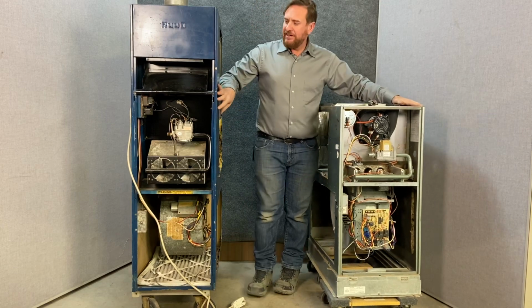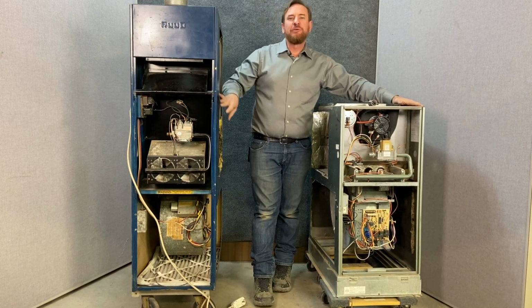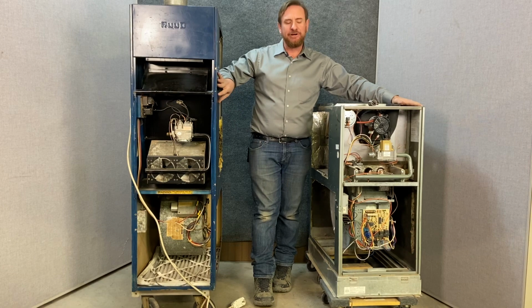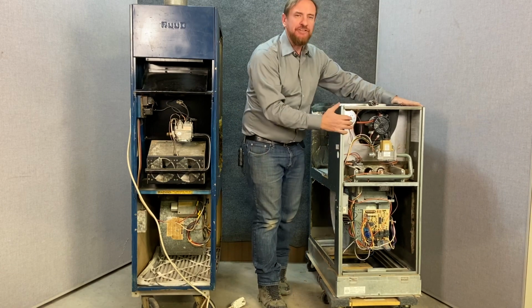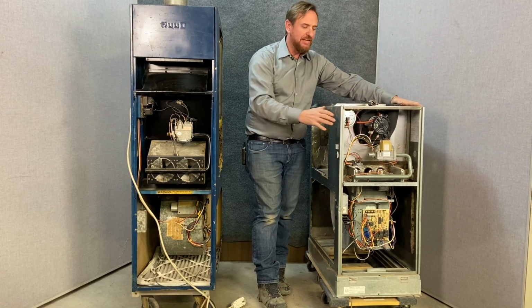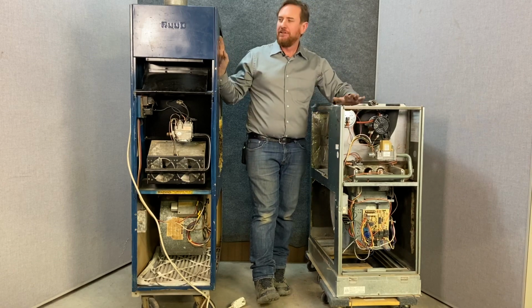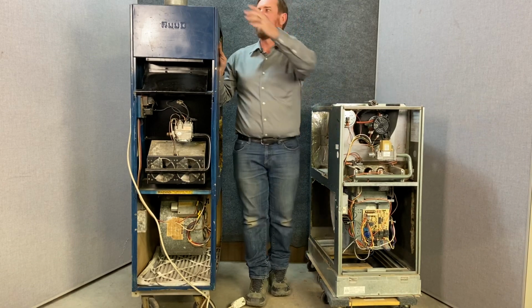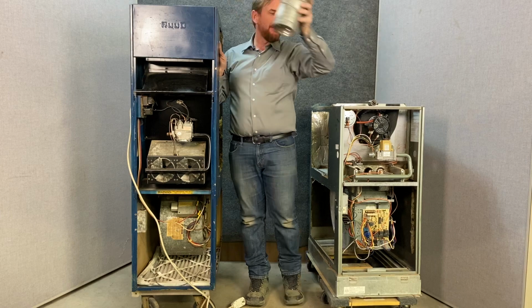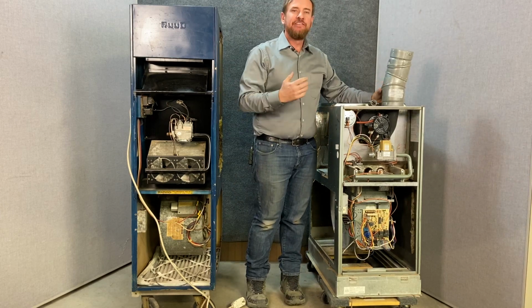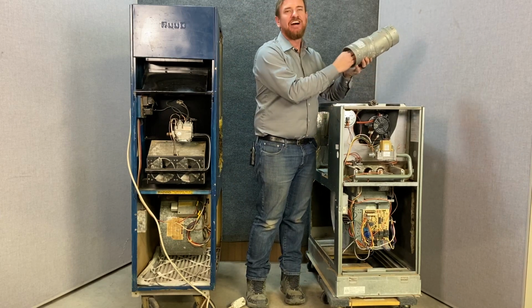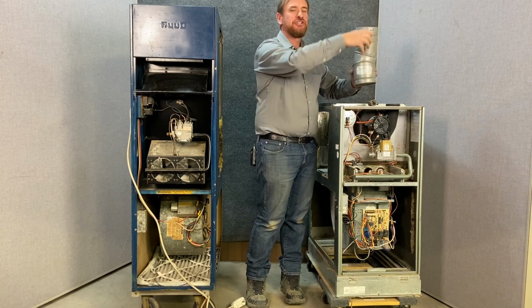This heat exchanger here, all the way up to this furnace, all the way up to 1991, 92, this is an 80 model. We talked about how much more efficient this system is, an 80% furnace, but both of these furnaces, they're still category 1 furnaces. It's still a natural draft flue pipe. The flue pipe in both of them are going to be very similar, as the hot gas needs to be a certain temperature so that it drafts out.